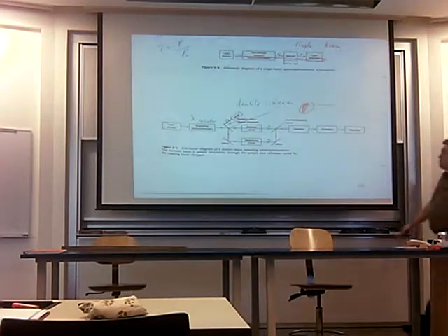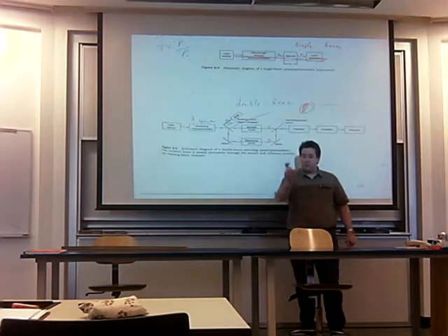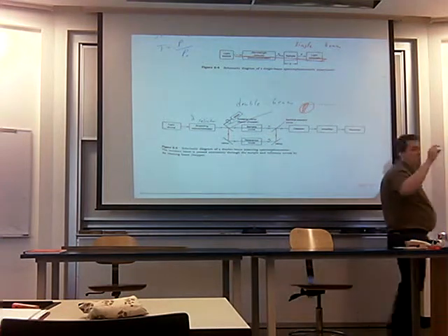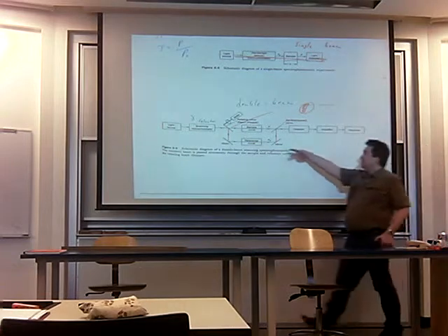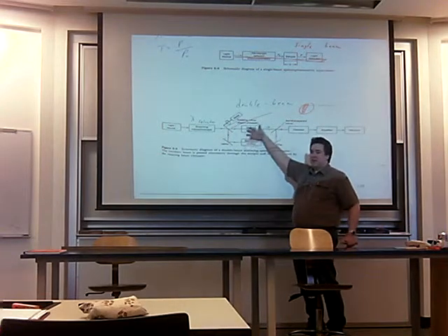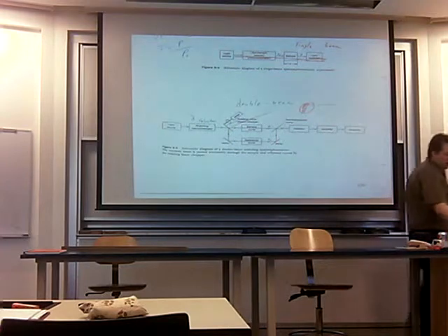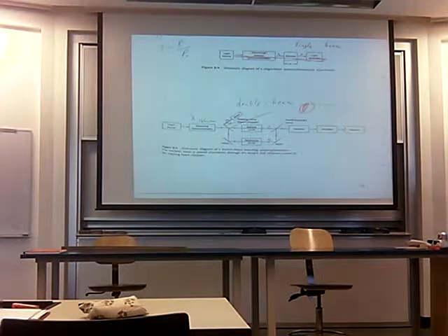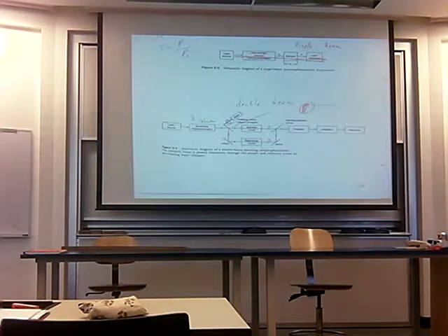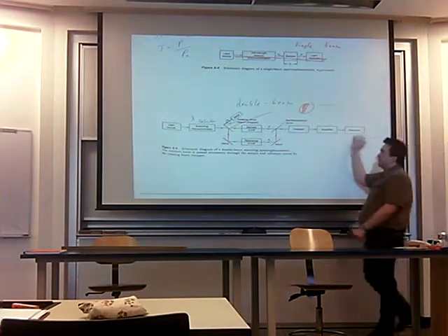So in a double beam instrument, you don't have to first put in your blank, then put in your actual sample. You put in your blank and your sample, and it's constantly taking the blank and taking the sample alternately. This leads to better results, more precise results, more accurate results. But it's a larger instrument, it's a more expensive instrument, it's got moving parts. So there are more things that can go wrong with this instrument.